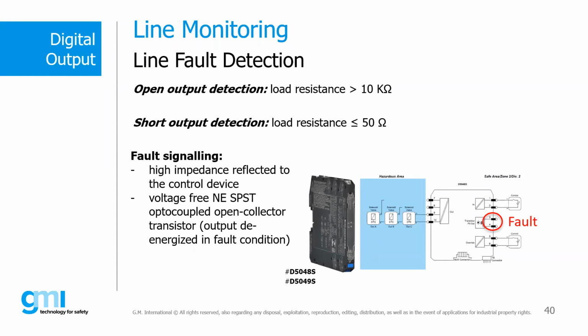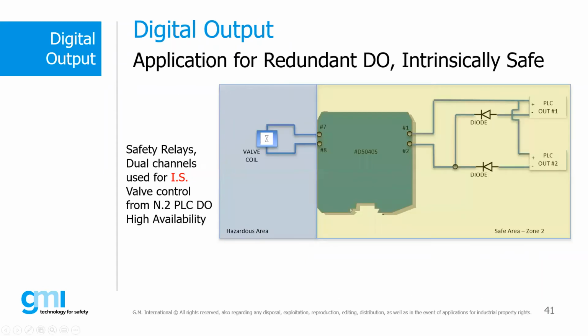Let's now take a look at the redundancy problem also for intrinsically safe digital output applications. Basically, there are three ways to obtain the redundancy of this system with three different levels of redundancy. The first redundancy system involves all the elements that make up the loop, from the valve in the field to the intrinsically safe barrier to the PLC card that controls the loop. This is certainly the most effective and safest redundancy system, but also the most expensive, as creating the redundancy of all elements of the loop has considerable cost.